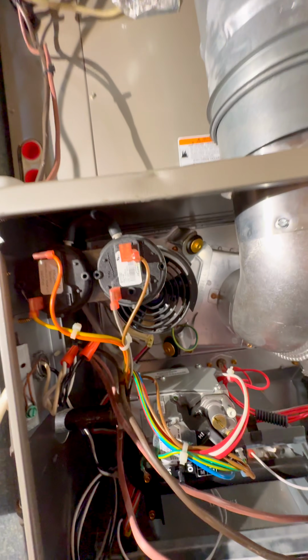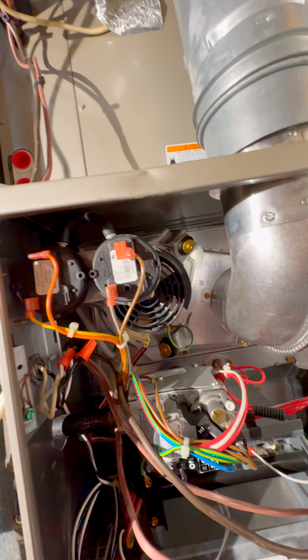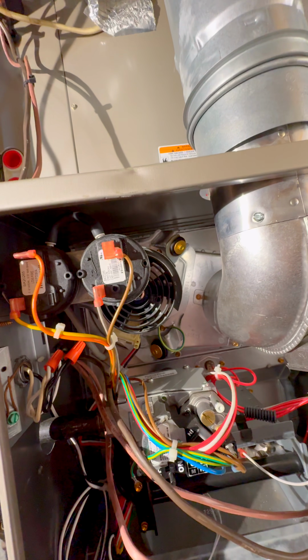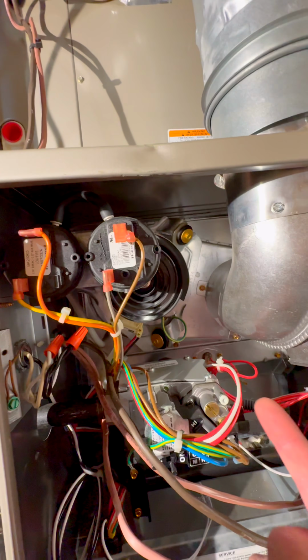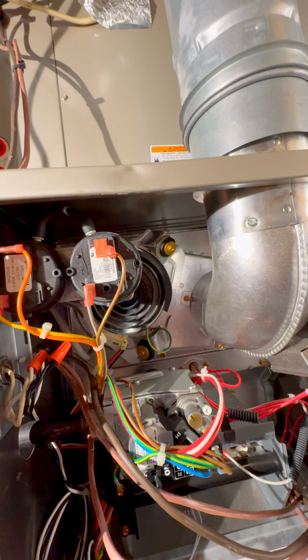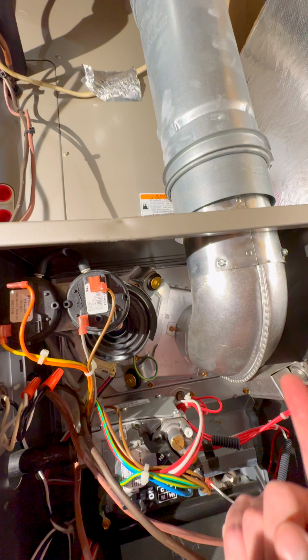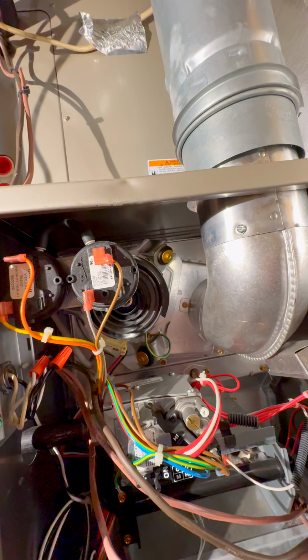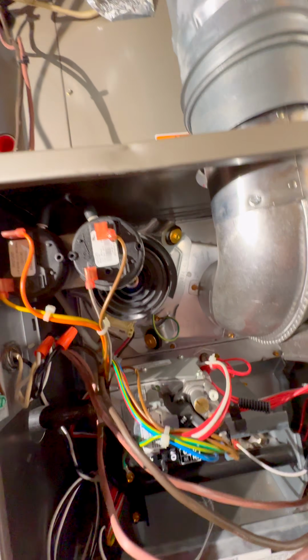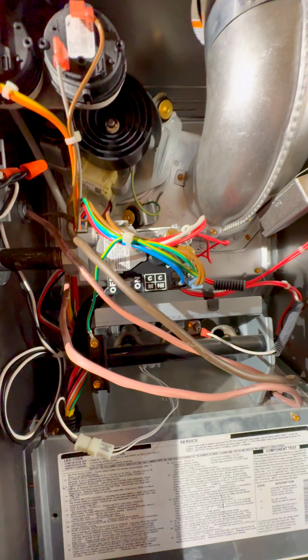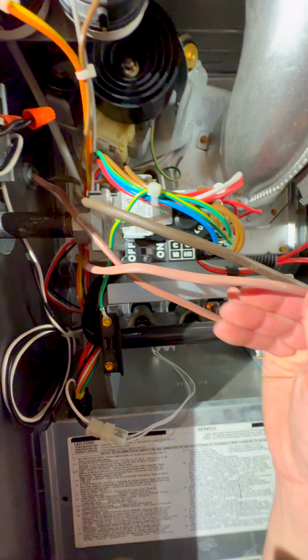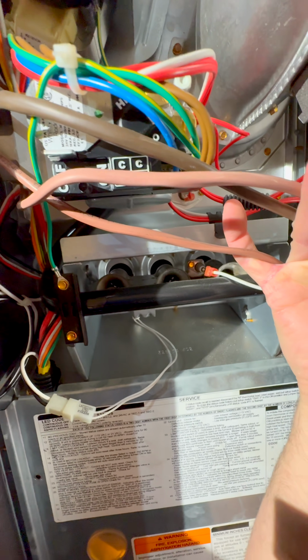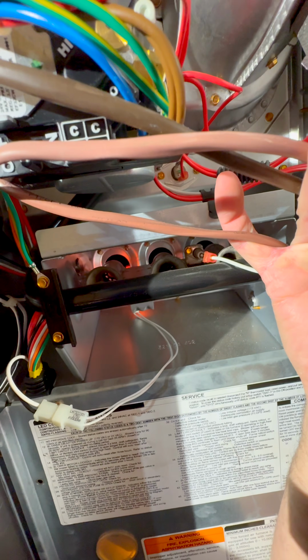I'm gonna get in here a little tighter, and momentarily we should get this inducer draft motor to come on. Go. All right, we got our inducer draft motor coming on. And right now that's proving that this vent can exhaust the combustible gases that we have. Our next step, now that we've got that taken care of, is we're gonna get down here to the ignition portion. In a few seconds, you'll start to see our hot surface igniter glow red.